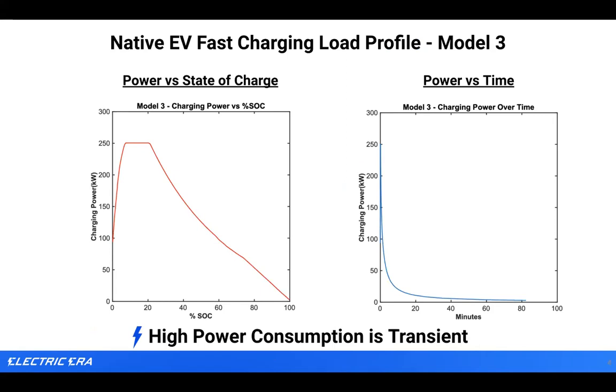We asked ourselves, at the first principles level, why is power so intensive and so problematic at DC fast charging stations? It really comes down to the native EV charging load profile, which you can see on screen for a Model 3. On the left-hand graph, you see charging power as a function of state of charge. The Model 3, when it starts, pulls and linearly increases from about 100 kW to 250 kW for maybe 5% of state of charge, then pulls at 250 kW for maybe 20% state of charge, and then linearly decreases down from there.